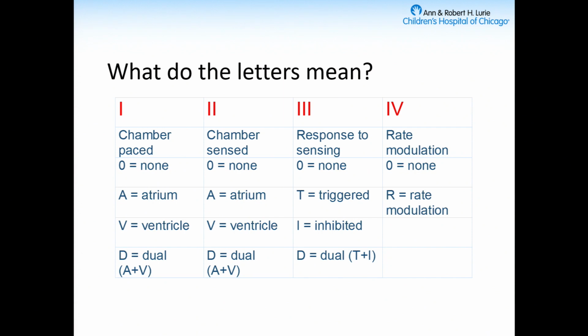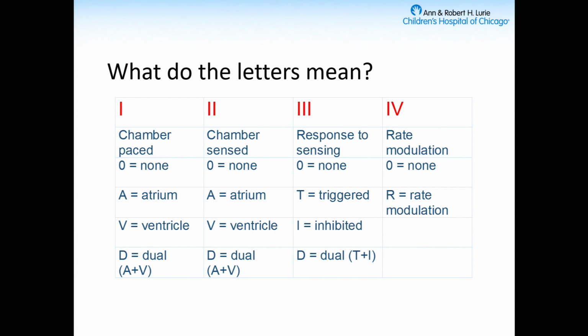The first letter, A or V, tells you about the chamber that's paced. If there's an O or a 0 in that position, then that means that there is no chamber paced. If there's an A, that means you can pace the atrium. A V, pace the ventricle. And a D means that the device is able to pace both, or dual, the atrium and the ventricle.